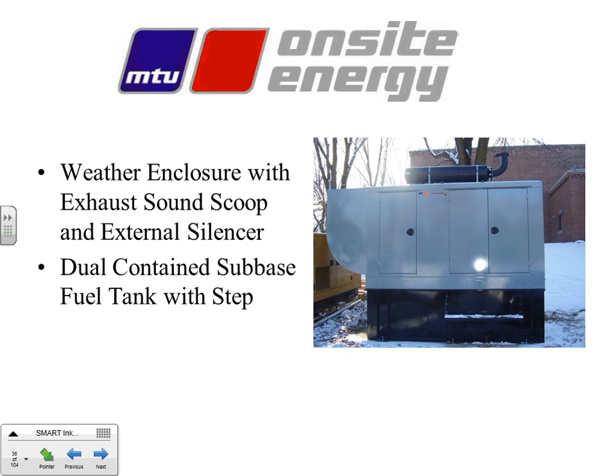This one is a good one to go over some of the things I was just telling you about. This one has the muffler on top. It also has a dual contained tank. So inside this black part, there's a tank that's down in this area, down to here, and up in here. There's some standoffs on the bottom that hold it off the bottom, so it's actually up and out. And there's a float switch that sits down in one of the corners here. I can't remember which one it is. But it comes down and just sits in there. If there's ever fuel in it, it pushes the float up, closes the circuit, and sends an alarm. Also, this one's got an external scoop.